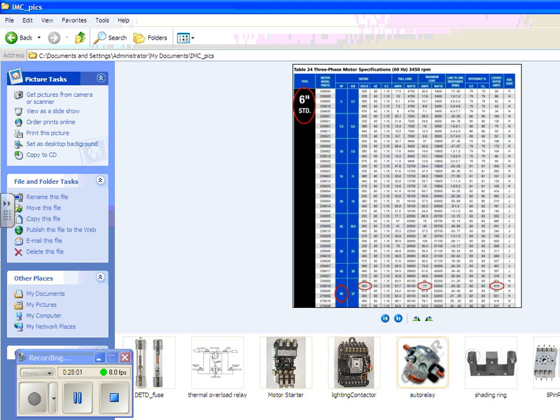Now, generally speaking, you're not going to do that. If it's over 2 horsepower, you don't want it 120 volts. Okay, if it's more than 1 horsepower, you don't even want it 120 volts. You want it 230 volts, or 240, whatever you want to say. And why is that? Keep the current down: lower current, lower voltage drop, lower inrush, lower everything. All right.